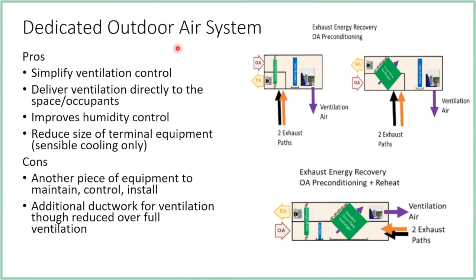So the benefit of doing the dedicated outdoor air system is you have a very simple ventilation control. It's one system that you have to worry about. You do get that ventilation air directly to your space occupants. You can improve humidity control because each of your terminal units in the space, they're dealing with the sensible load in the space, the humans, the computers, the lights, everything in the space. And this system is designing the ventilation load, which is really focused on that humidity control or humidity requirements for the outdoor air.